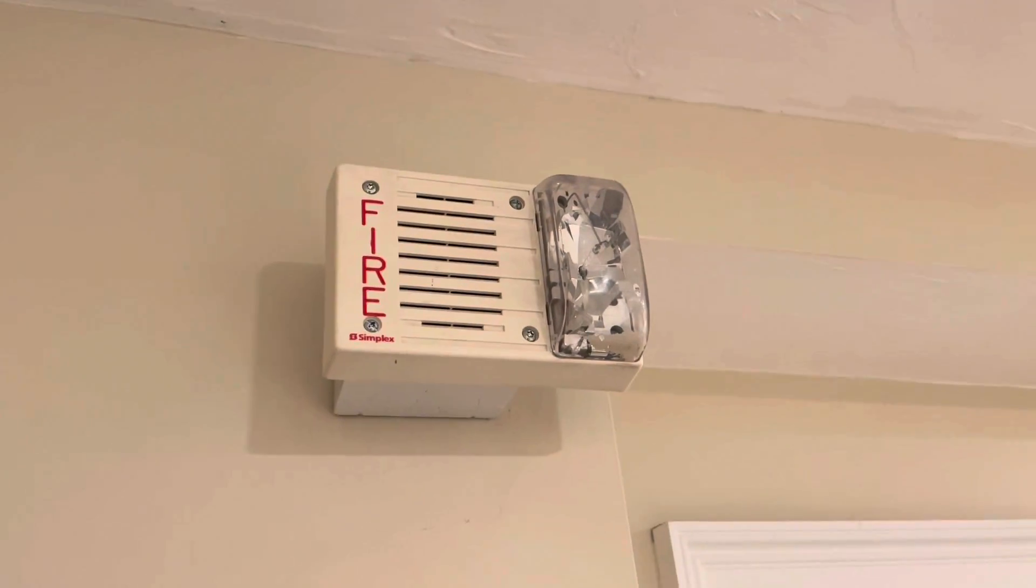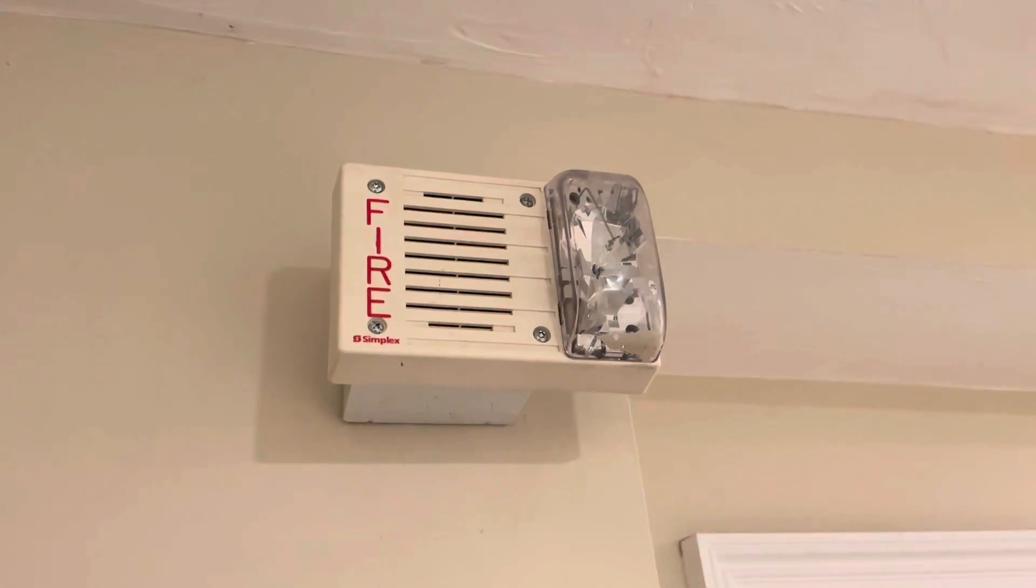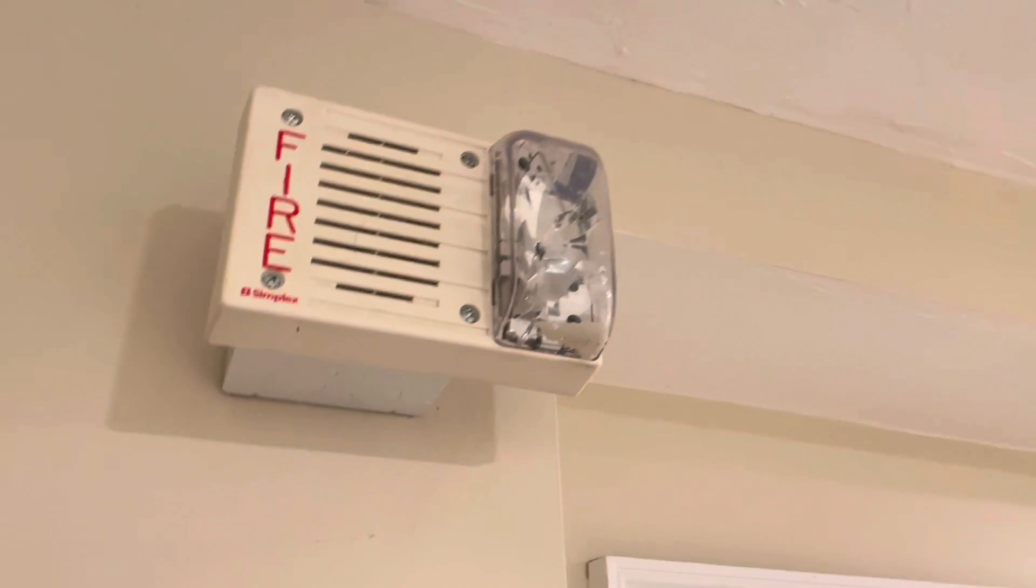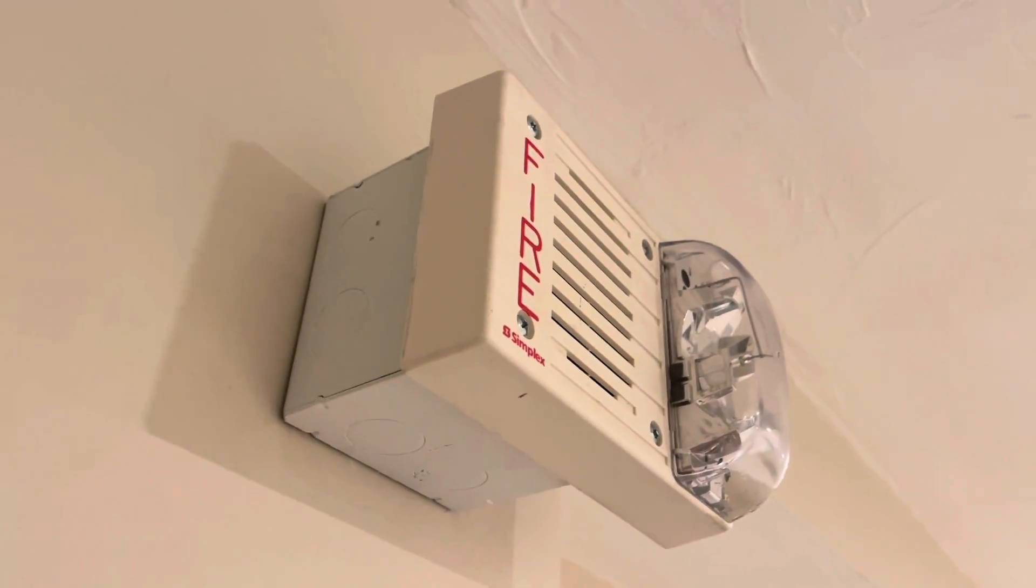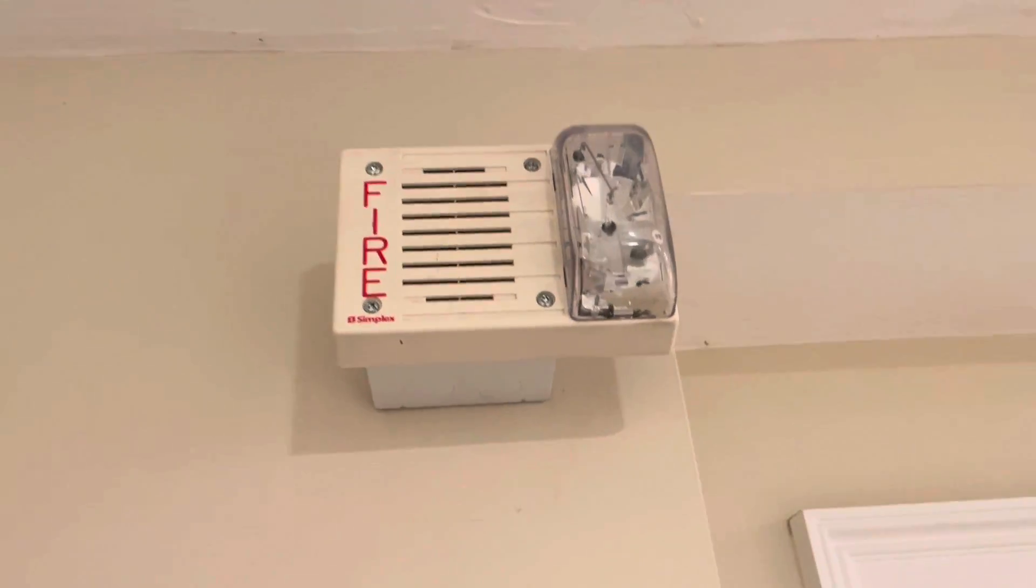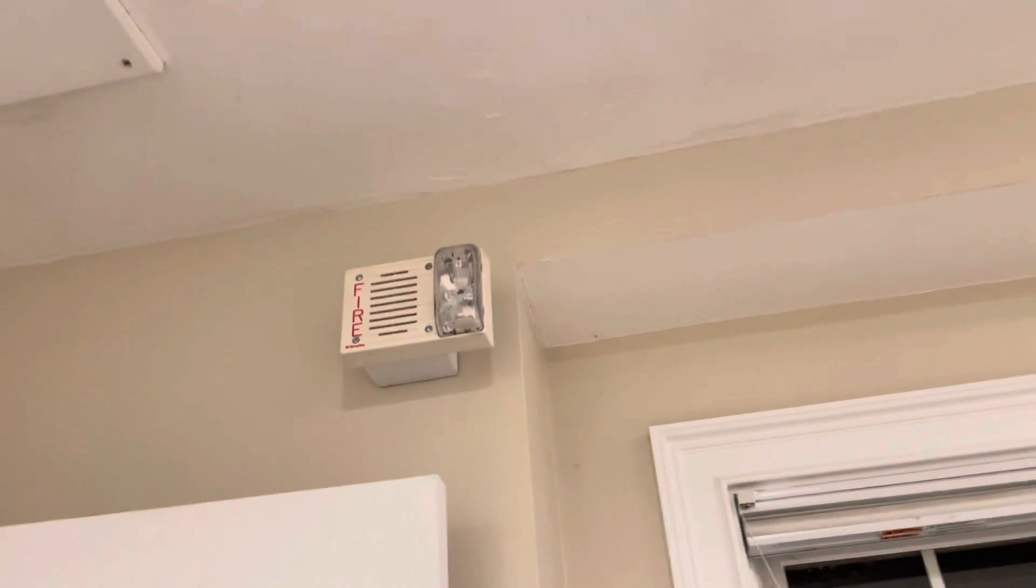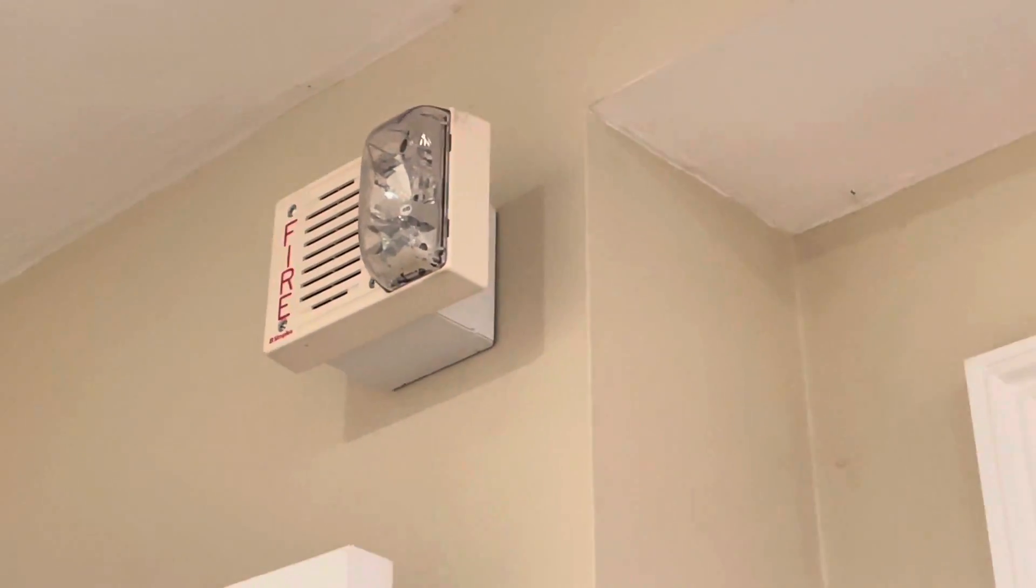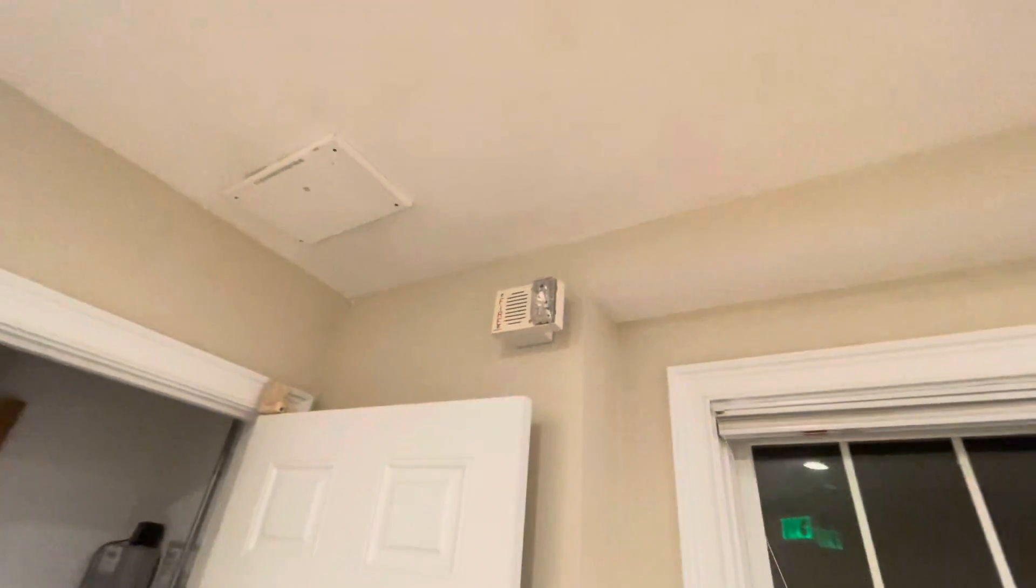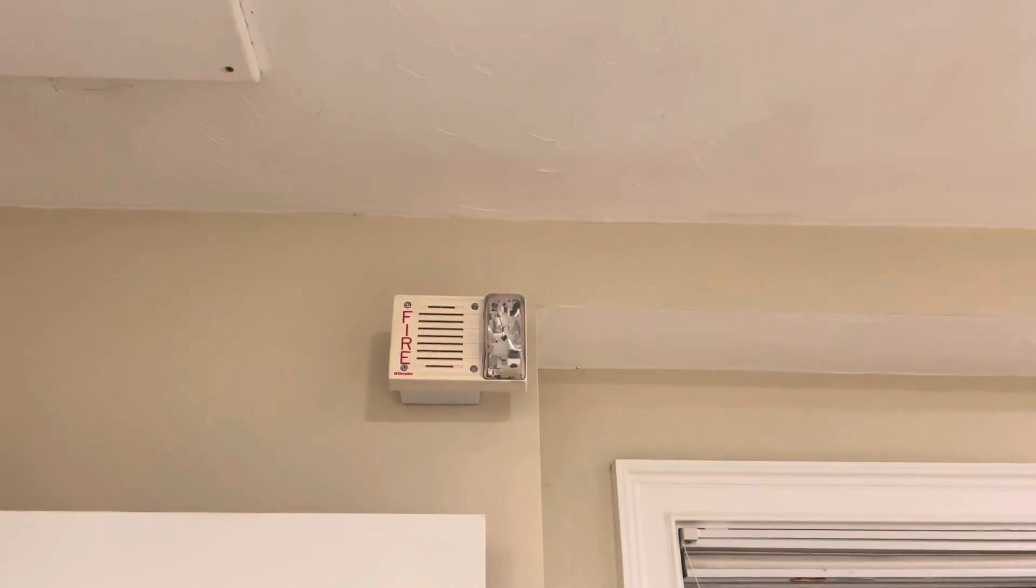So the device on this side of the basement is the same speaker strobe except it's white again syncable strobe. The back box for this is a 4x4. Technically you're not supposed to use a 4x4 box but I didn't have a white simplex back box. This is a three inch deep box so it's slightly deeper than a standard 4x4 but it fits the speaker strobe perfectly and it looks pretty nice.